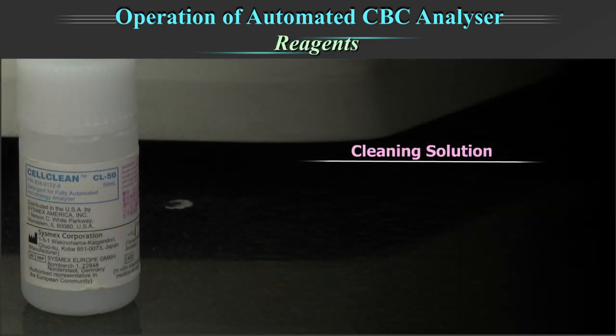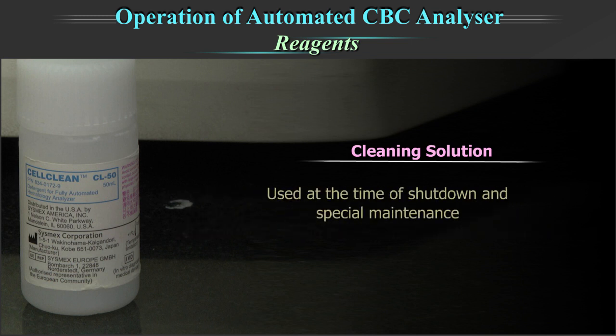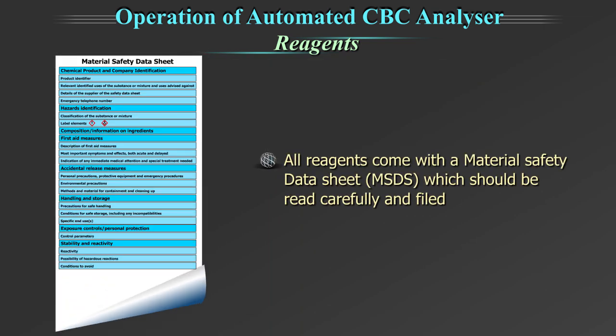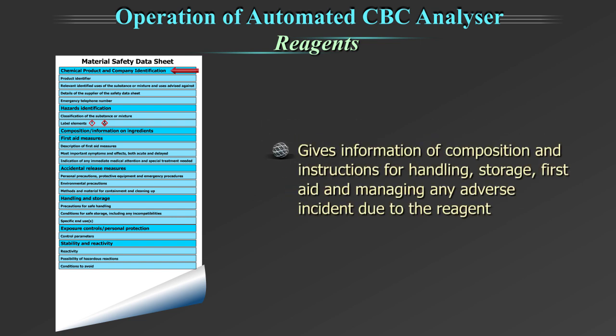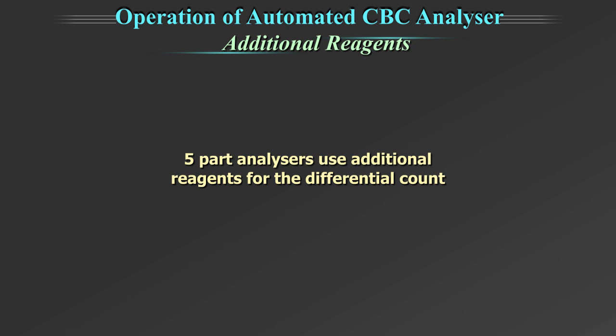The cleaning solution — for example, cell clean — is used to clean the instrument. It removes residuals of lysing reagent, cellular residues and blood proteins from the hydraulic systems, detector block, block aspiration tube and flow cell. It is used at the time of shutdown and special maintenance. All reagents come with a material safety data sheet (MSDS) which should be read carefully and filed. It gives information on composition and instructions for handling, storage, first aid and managing any adverse incident due to the reagent.